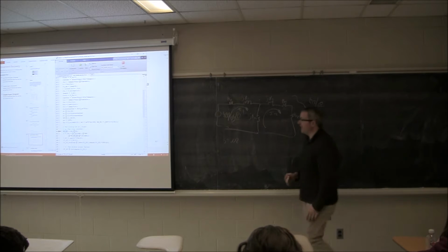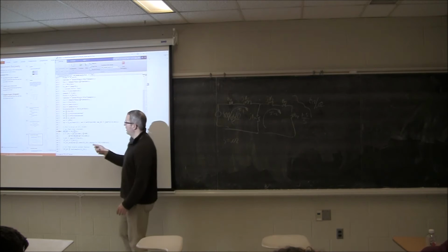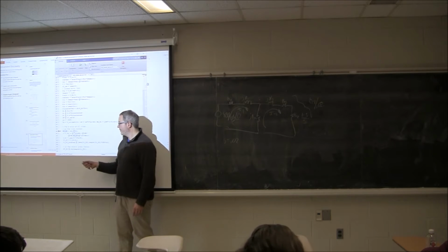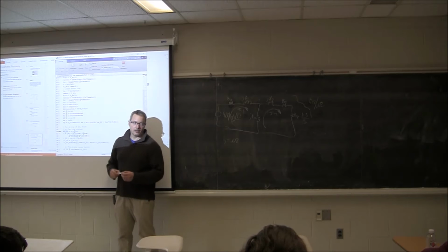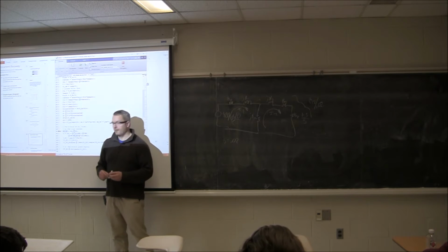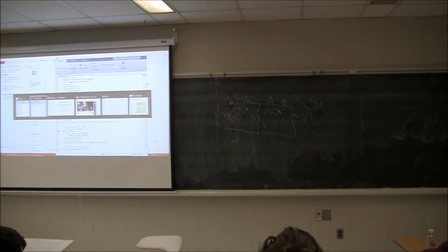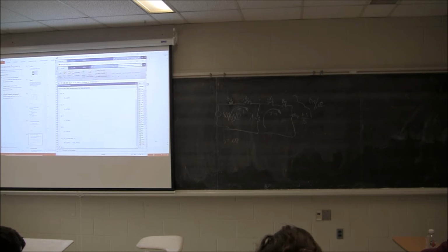And then I just pull out my value of I1 for 2% slip. Okay? The value I get is 38.5 at an angle of minus 33.79.